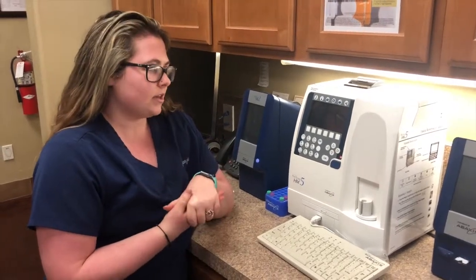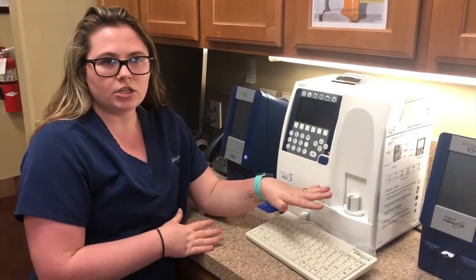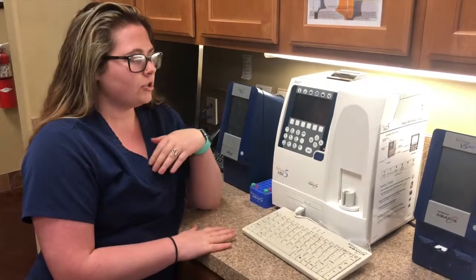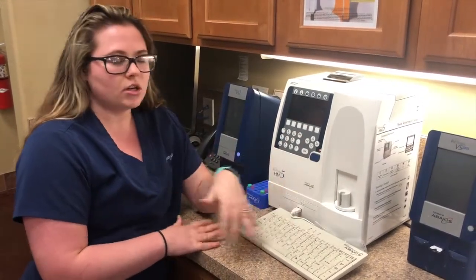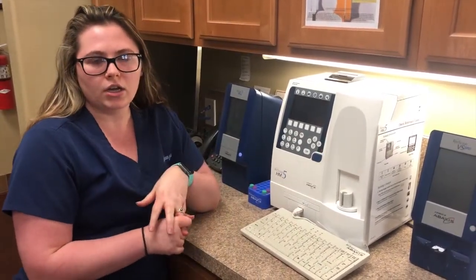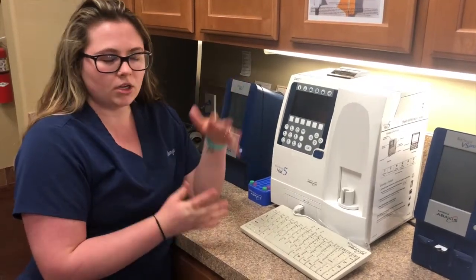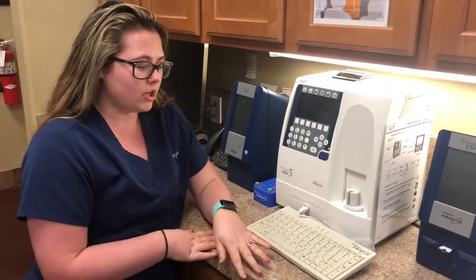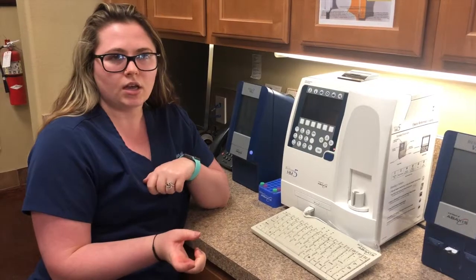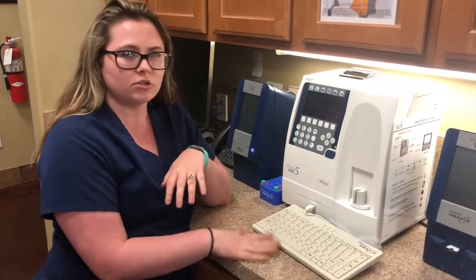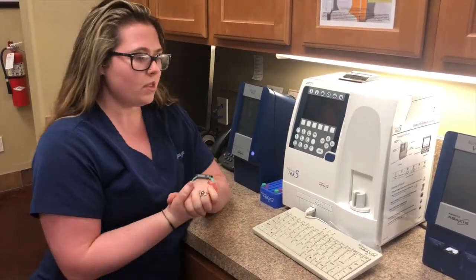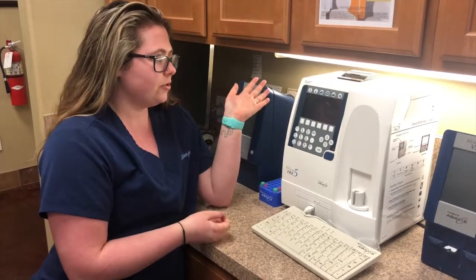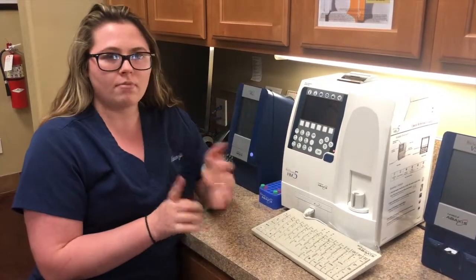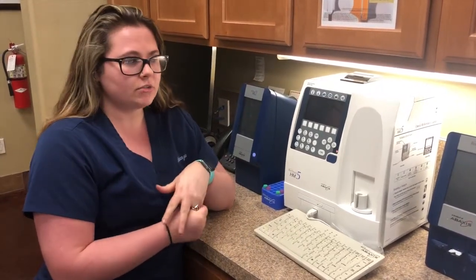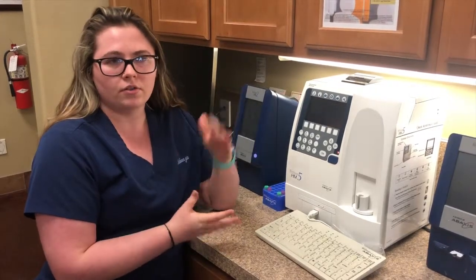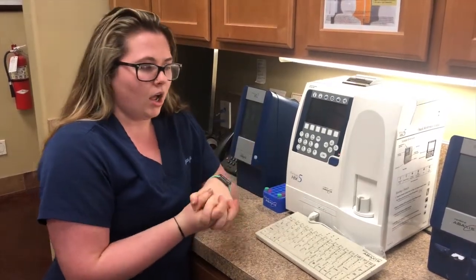So our weekly maintenance that we're going to do is just kind of wipe down our machine with a non-bleach product. We just want to make sure there's no dust and all of it's lint-free, hair-free, to make sure everything's running properly. We're also going to clean our keyboard with the can of air that you just spray on the keyboard to make sure there's no dust and everything on that as well. What we're also going to do monthly is we run a prime and a clean cycle. This is just to make sure everything works well and all of our results come out as needed.